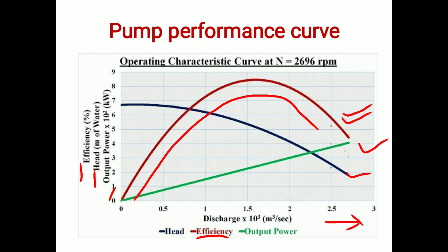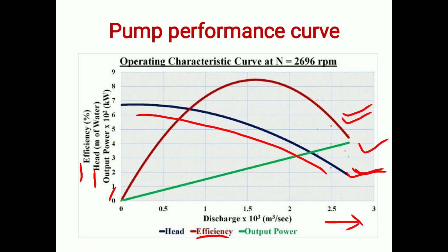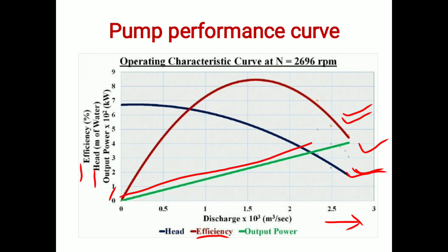After the best efficiency point, if we further increase the discharge, our pump efficiency will decrease. The next curve is head versus discharge: when we increase discharge or flow, pump head decreases, and vice versa — when we increase pump head, discharge decreases. The last curve is output power, which is directly proportional to discharge. When we increase pump discharge, the power requirement also increases. Note that this single curve is plotted for a constant RPM and constant impeller diameter.